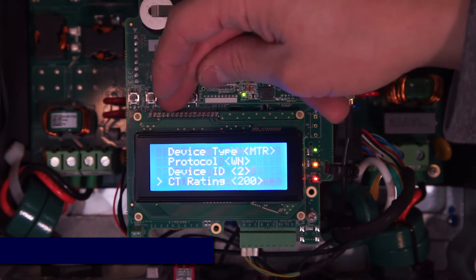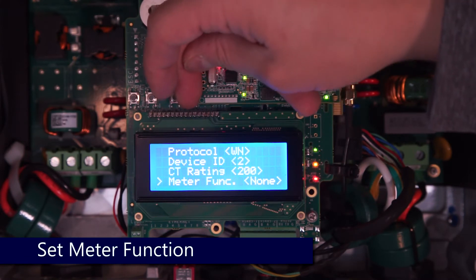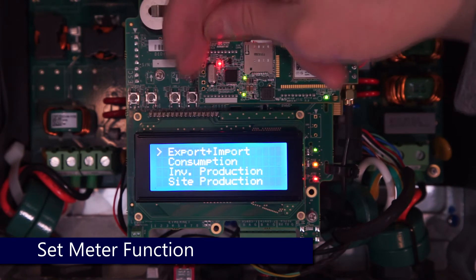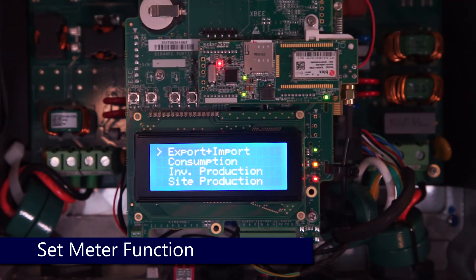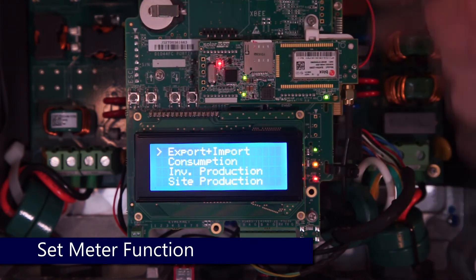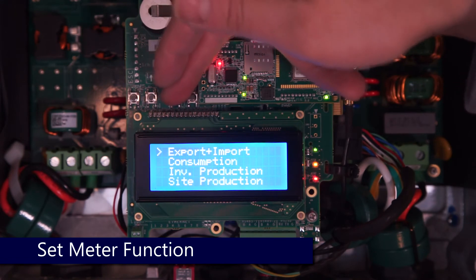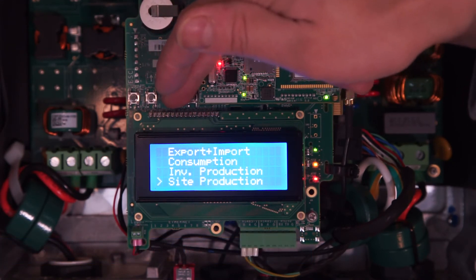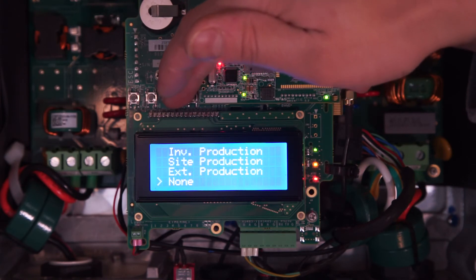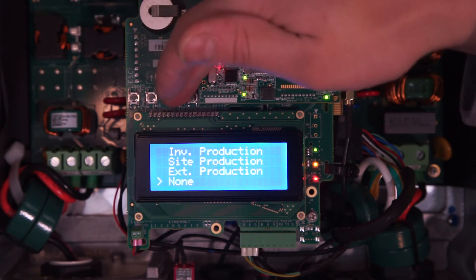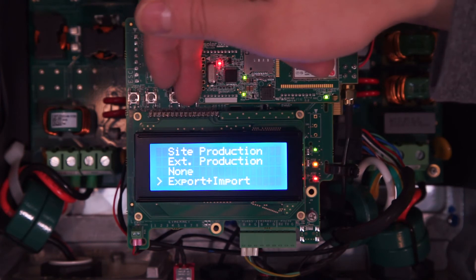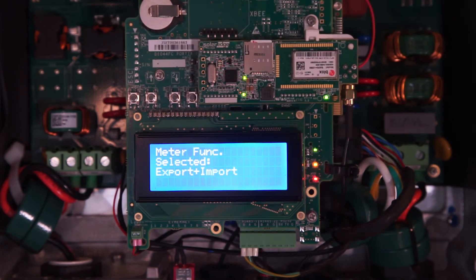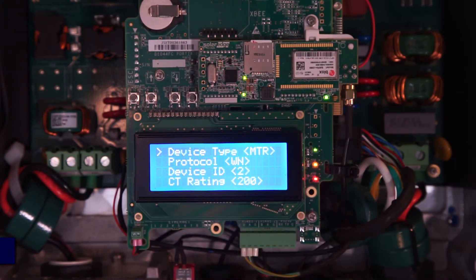Next we'll need to set the Meter Function. We're going to be setting this up for Export and Import. We'll quickly scroll through all of our options. Our CTs are placed in between the house and the grid, with CTs facing the grid, so we'll be setting it up for Export and Import.